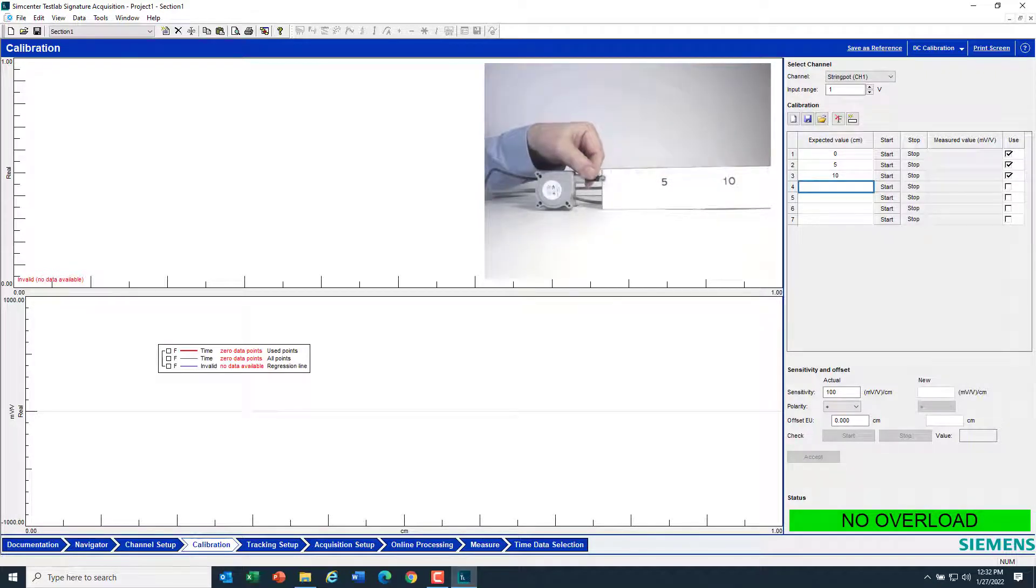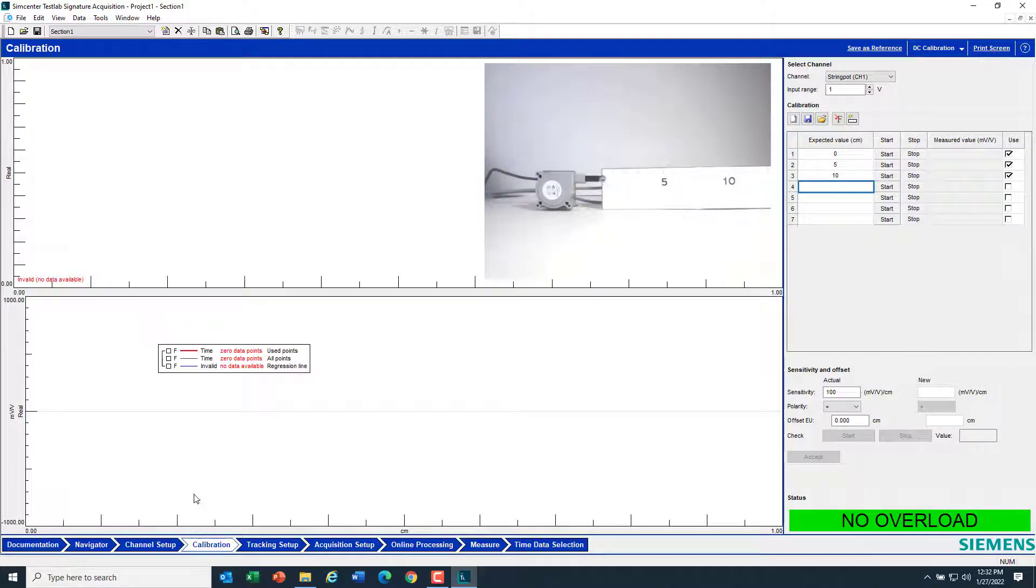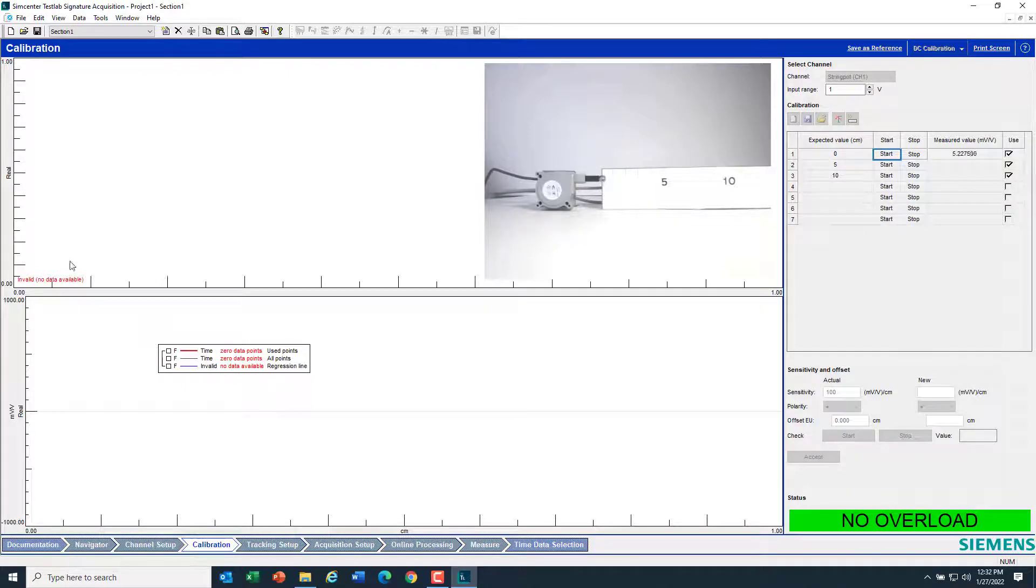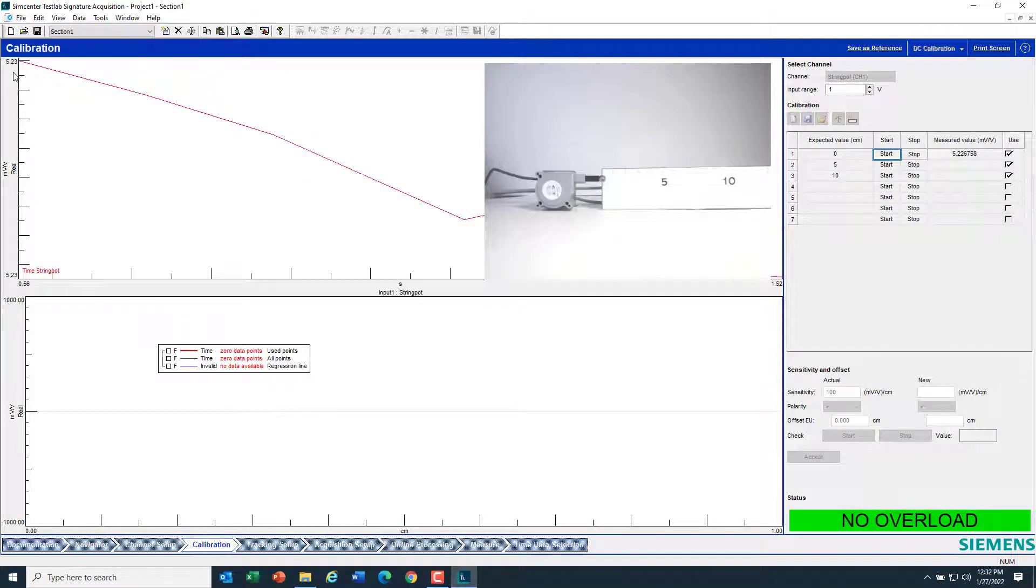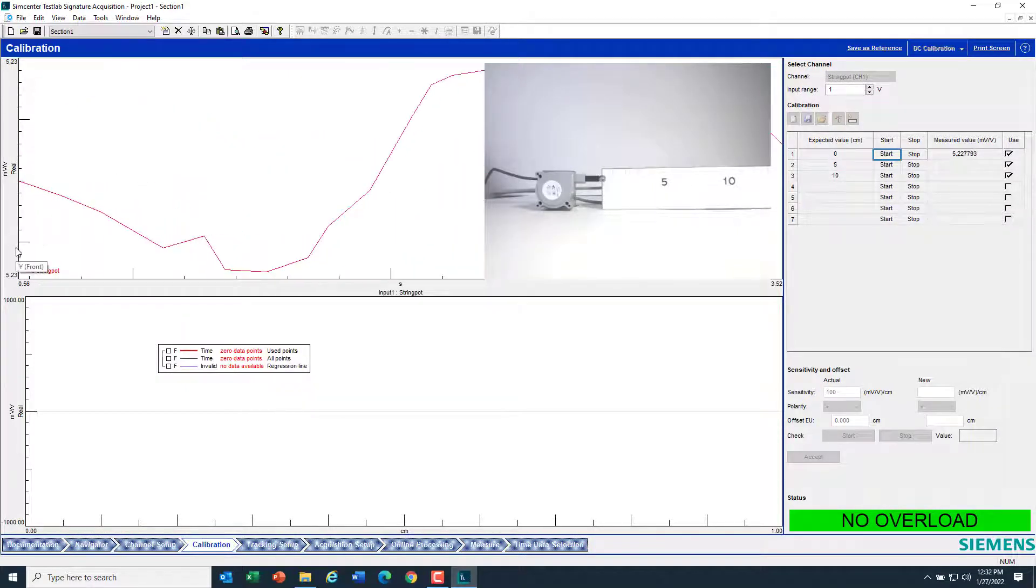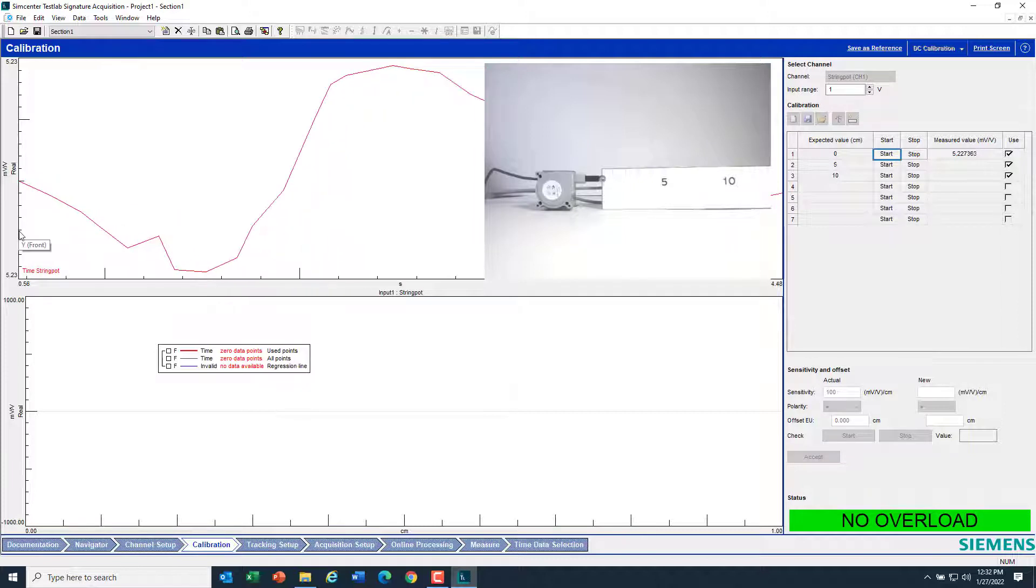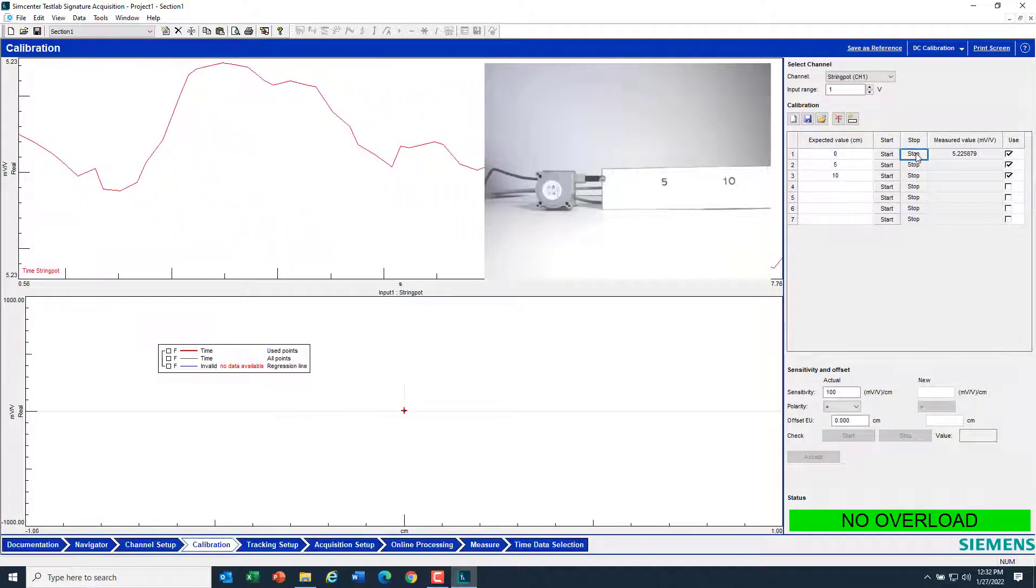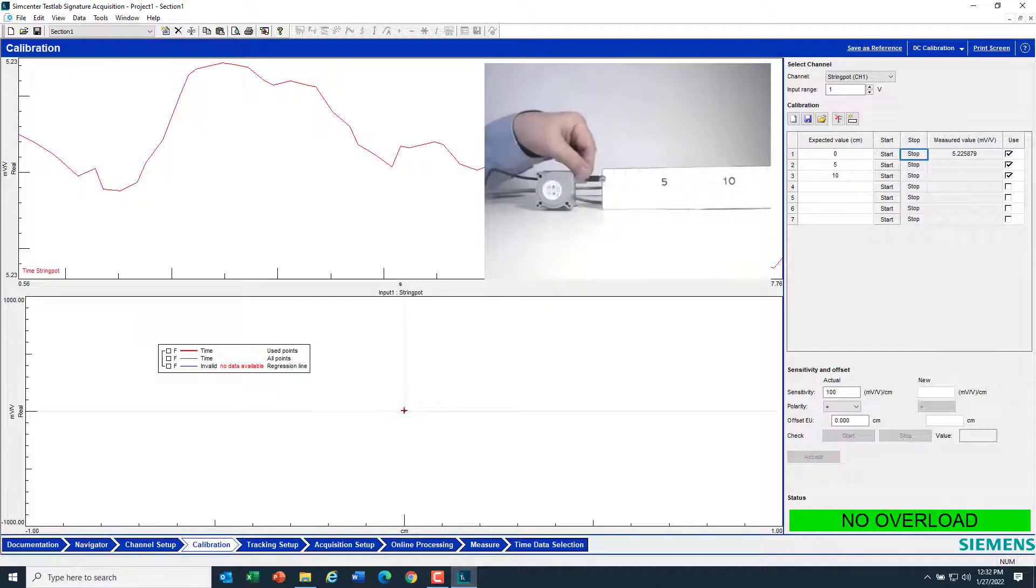I'll put a measuring device over here. You might have something that's a little more elaborate or thorough. But right now, you can see that I have the string pot located at 0, so I'll measure the 0 value. And it shows that voltage over here. This is auto-scaled, so don't worry if it's going up and down because these are very minute differences. When it's done measuring, or I can hit stop, I've measured the 0 value.